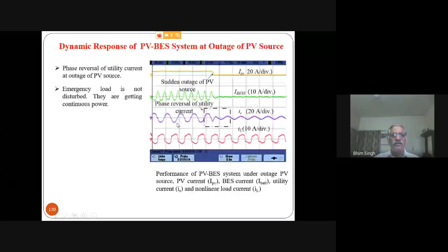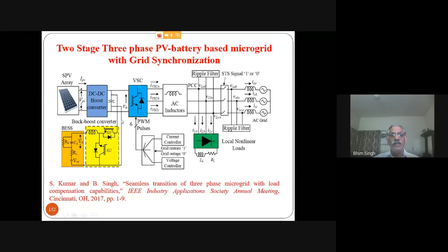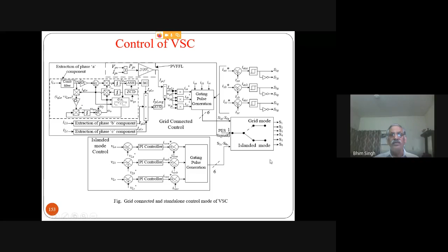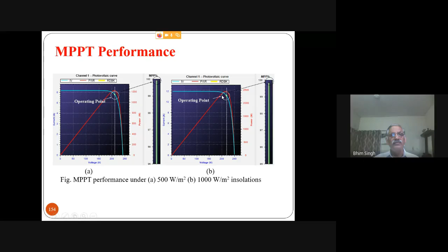The same thing we did in the 3-phase case also: we put a battery here, and now all those features are taken care of, the intermittency of the generation, the intermittency of the load, and the intermittency of the grid as far as the load is concerned. You can call it a filtering of the load. In islanding mode it works virtually like a UPS, where you give a 3-phase reference voltage. You have the load voltage, then the inverter current: the outer loop is the voltage control and the inner loop is the current control, and that takes care of operation in islanding mode. Otherwise, in grid connected mode, it works in the same way as I discussed.